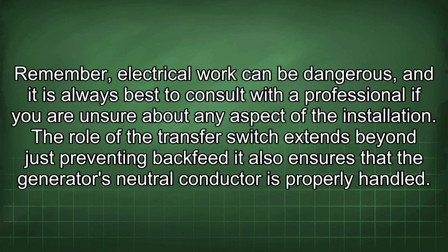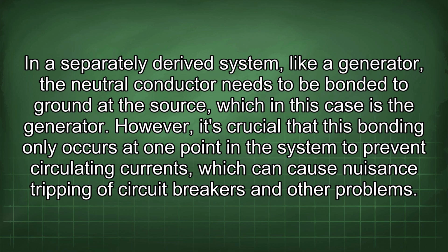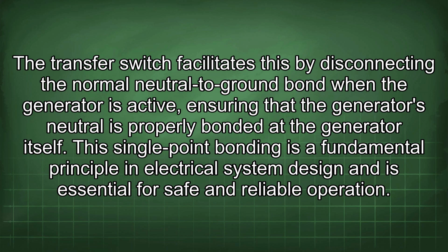The role of the transfer switch extends beyond just preventing backfeed. It also ensures that the generator's neutral conductor is properly handled. In a separately derived system, like a generator, the neutral conductor needs to be bonded to ground at the source, which in this case is the generator. However, it's crucial that this bonding only occurs at one point in the system to prevent circulating currents, which can cause nuisance tripping of circuit breakers and other problems. The transfer switch facilitates this by disconnecting the normal neutral to ground bond when the generator is active, ensuring that the generator's neutral is properly bonded at the generator itself. This single-point bonding is a fundamental principle in electrical system design and is essential for safe and reliable operation.